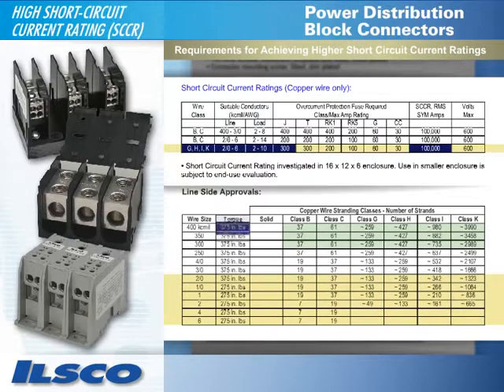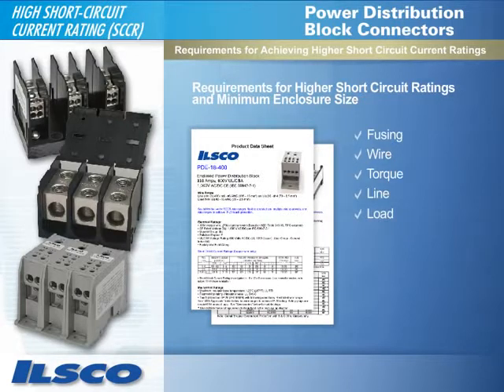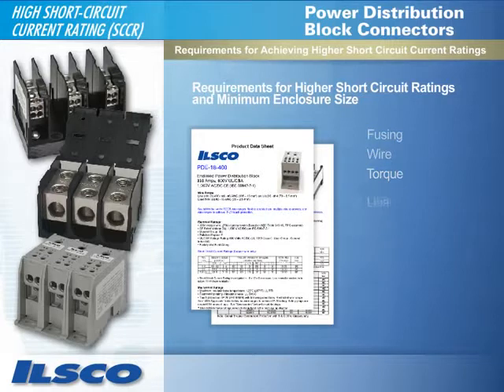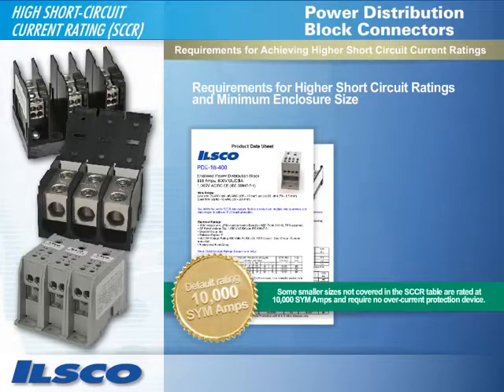Remember, the specified fusing, wire selection, and torque requirements must be followed in conjunction with the proper combination of line and load conductors in order for the block to be rated at 100,000 SYM amps. If the specified fusing, wire selection, and torque requirements in the SCCR table are not used, all power distribution blocks have a default rating of 10,000 SYM amps with the standard wire range. Some of the smaller sizes not covered in the SCCR table do have the 10,000 amp rating, which requires no overcurrent protection device.